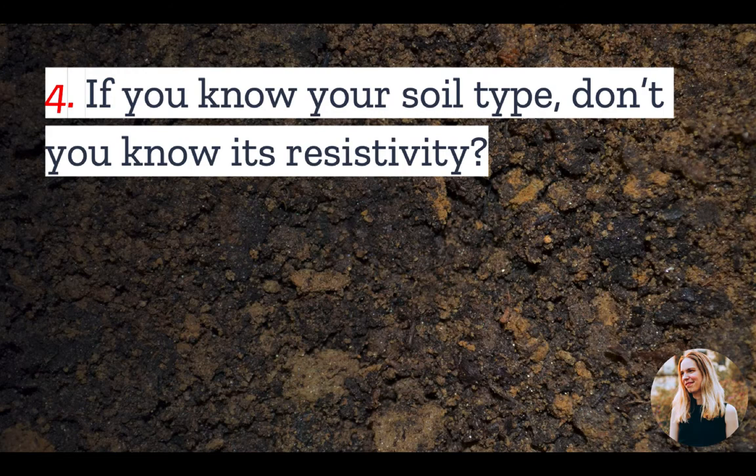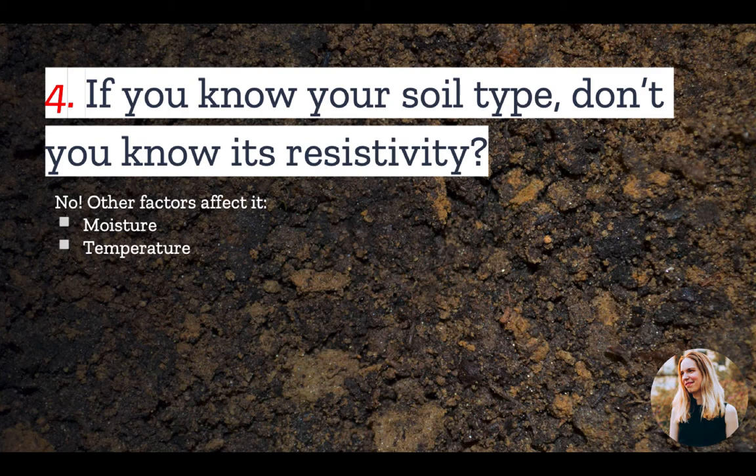Number four: why do you have to bother testing? If you already know your soil type on your land, don't you automatically know its resistivity? Well, the answer is no. Soil classification can provide only a rough estimate of soil resistivity, as other factors affect it as well, such as moisture content, temperature, organic matter, and the depth of the soil.